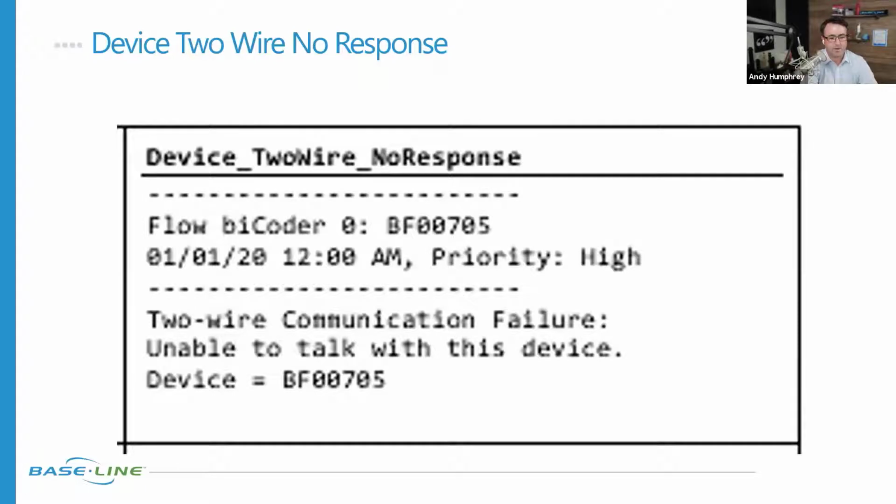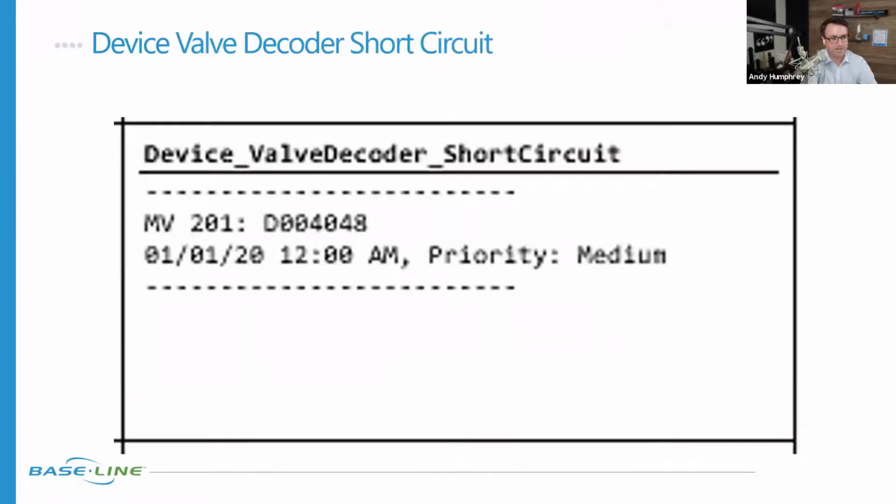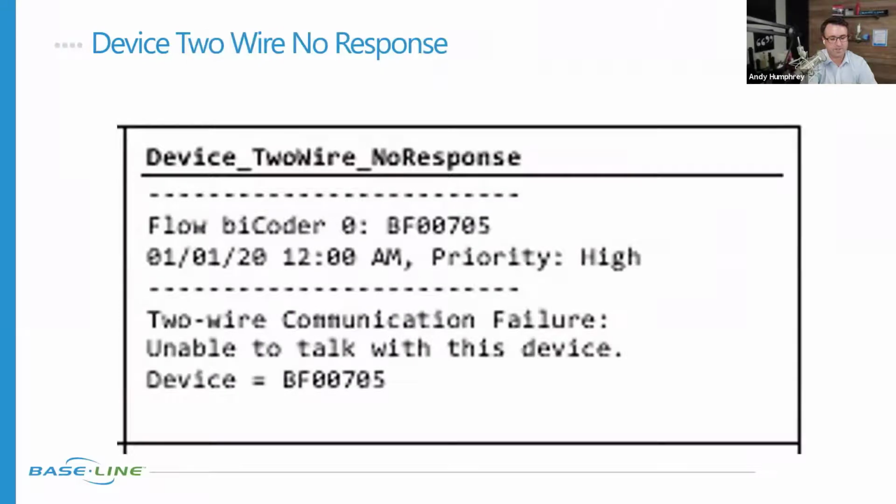Nice. Okay. And just to add full clarity, sometimes we see this message. Again, it's telling us that the signal went out, but it didn't come back. So we also see this occasionally when a system is out of 2-wire specification, so they've run a wire way too far.